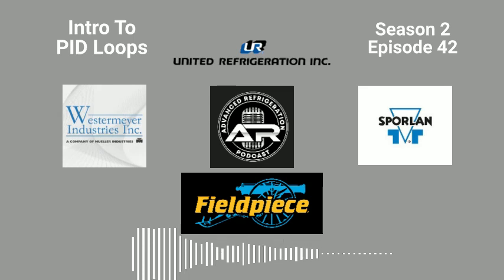For sure. Trimming out pulse valves, I get them close to where they're not overshooting superheat, and I'm not having case temp issues. But don't waste all the time in the world trying to tune out pulse valves. It's just a losing battle. But with steppers, like Brett said, make sure everything is correct first. Make sure it's the right steps and it's zeroed out, because if you're trying to control it like that, there's going to be definite issues. And then try to find your base values.